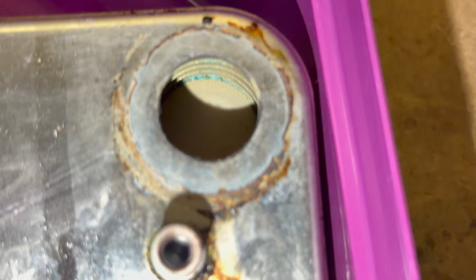I'd rather replace, but if you've got a dirty central heating system full of magnetite and sludge, why would you bother putting in a new plate without cleaning the system? So I think actually cleaning this out is a waste of time unless you actually clean the central heating system. But because this is only an experiment, I'm going to try and clean it out.